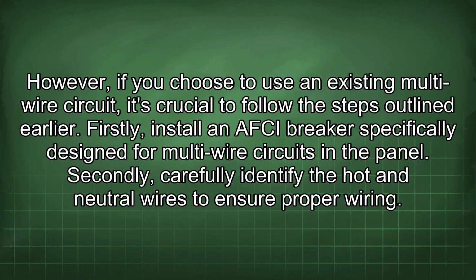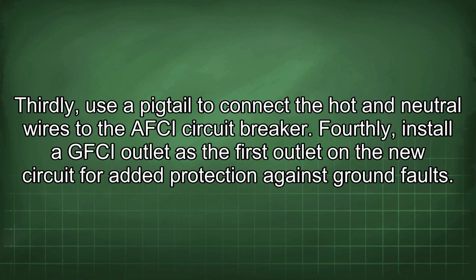Firstly, install an AFCI breaker specifically designed for multi-wire circuits in the panel. Secondly, carefully identify the hot and neutral wires to ensure proper wiring. Thirdly, use a pigtail to connect the hot and neutral wires to the AFCI circuit breaker. Fourthly, install a GFCI outlet as the first outlet on the new circuit for added protection against ground faults.